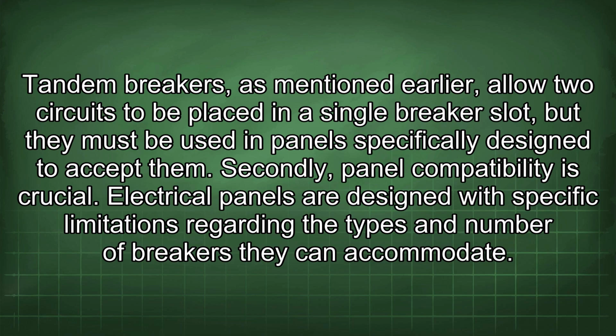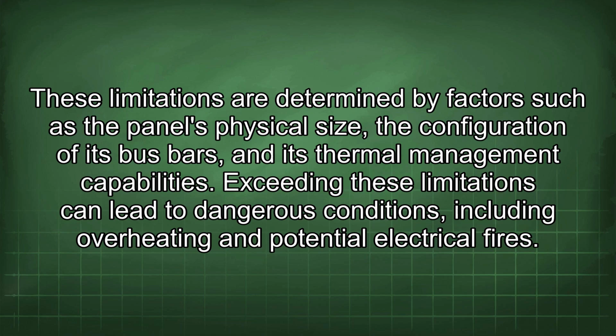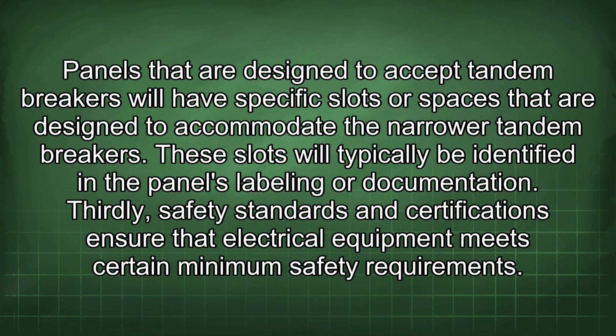Secondly, panel compatibility is crucial. The electrical panels are designed with specific limitations regarding the types and number of breakers they can accommodate. These limitations are determined by factors such as the panel's physical size, the configuration of its bus bars, and its thermal management capabilities. Exceeding these limitations can lead to dangerous conditions, including overheating and potential electrical fires. Panels that are designed to accept tandem breakers will have specific slots or spaces that are designed to accommodate the narrower tandem breakers. These slots will typically be identified in the panel's labeling or documentation.